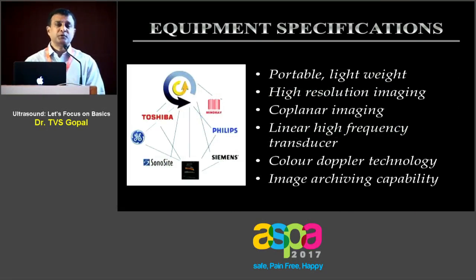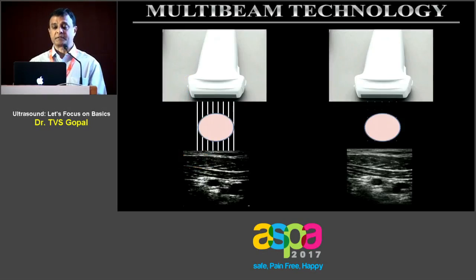So if you wish to buy an ultrasound machine, today you have a cafeteria choice. There are so many manufacturers in the market, which is good for us because it eventually helps in bringing down the cost of these machines. But you would want this machine to be portable, lightweight. You would want the machine to give you a very good quality of the image. And you would want at least one transducer, which is a linear high-frequency transducer. The machine should have color Doppler, and you should be able to archive your images so that you can retrieve them and use them at educational events such as this.